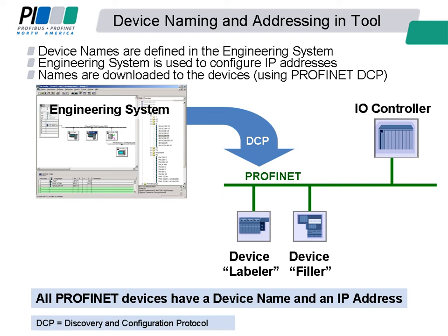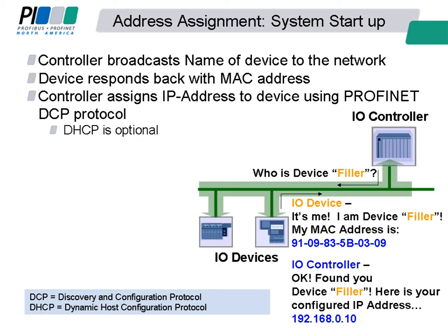One important concept we must mention is naming. With Profinet, all devices on the network have a device name for easy management. Device names are defined in the engineering system as well as IP addresses. The device names are then downloaded to the devices using the Profinet DCP protocol. The device name is used for startup, and the I.O. controller finds the devices by their name and sets their IP address automatically.